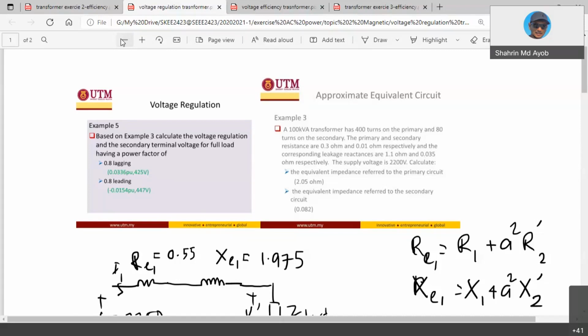A good transformer has what we call a good voltage regulation, meaning there is a slight difference between no load voltage and full load voltage at the output side. This means the losses, the voltage drop inside the transformer, is very minimum. So if you have a voltage regulation that is very small, your transformer is very good - that is the indication. Voltage regulation is the second main part in the transformer.